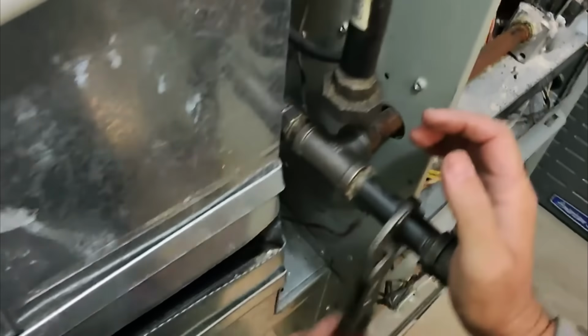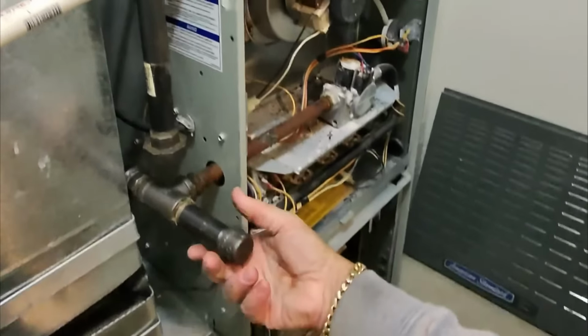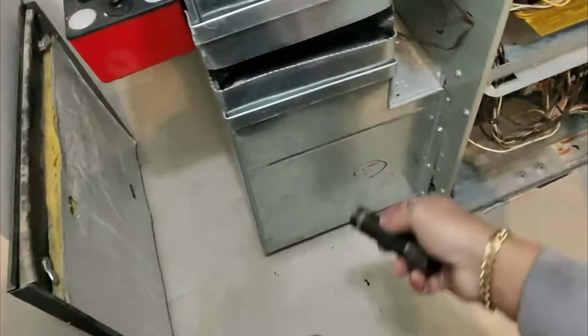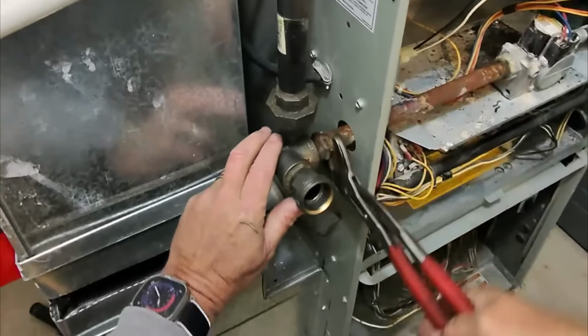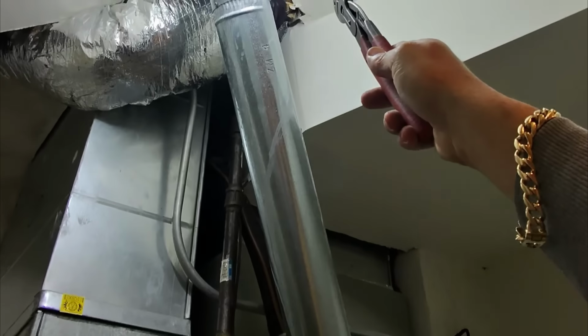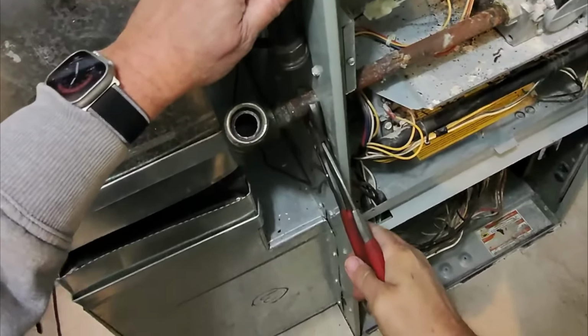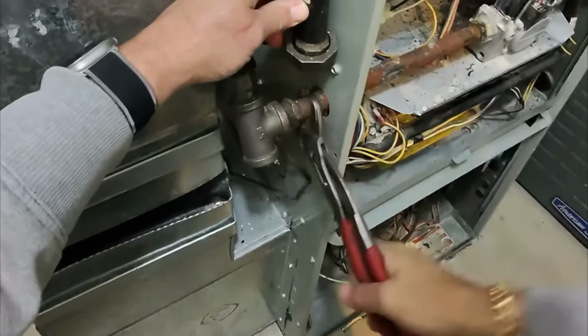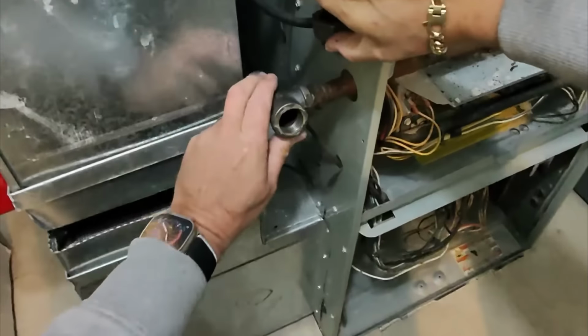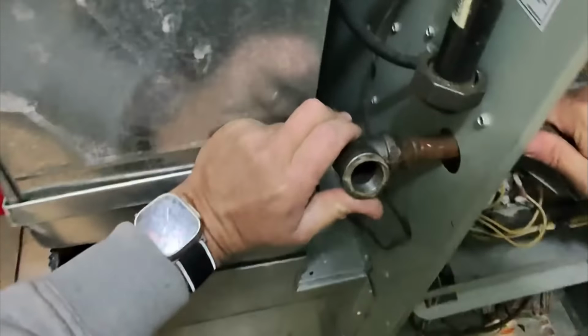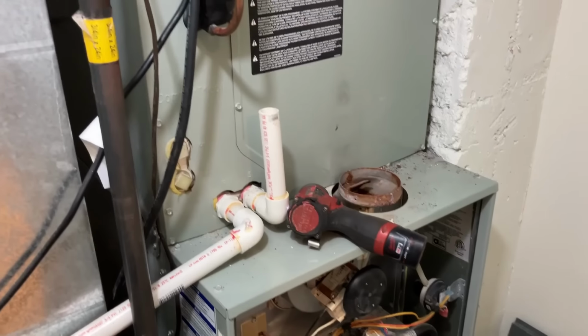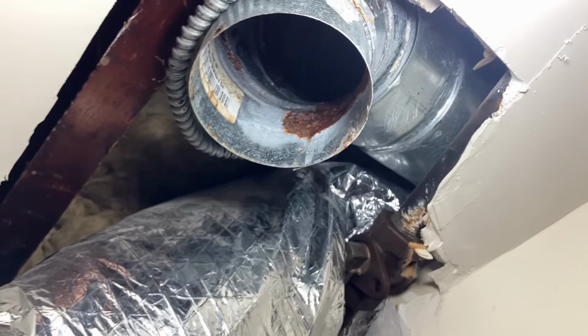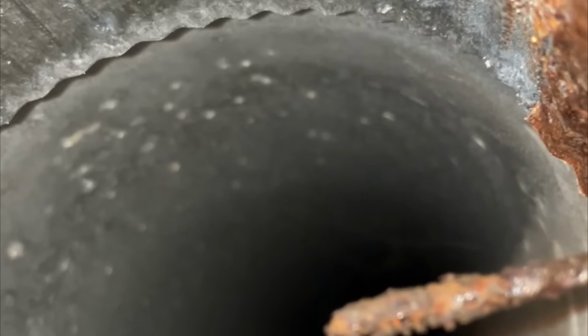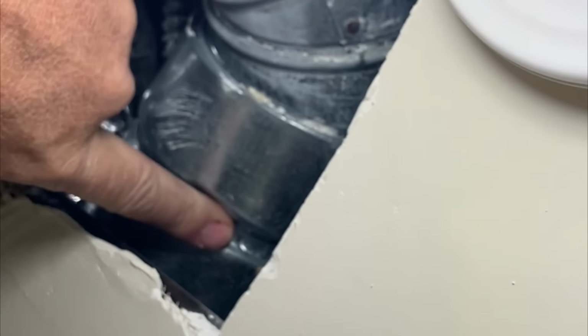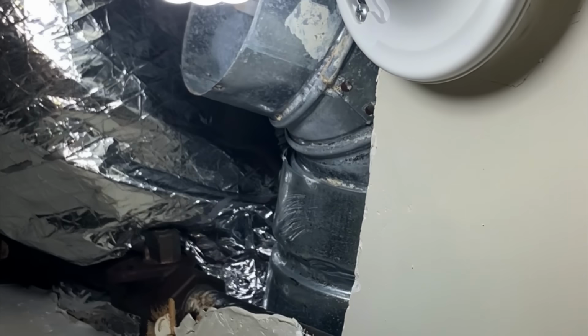All right, let's disconnect the gas. Gas valve is off there. Now, what's fascinating about this install is that whoever installed it thought it was a great idea to pretend that they're using B-vent, but they don't. And I'll show you a little bit later what I'm talking about, because it's quite sad. But as they say, or as I say, hacks bring stacks. All right, and in case you guys don't believe me, let me show you. See, that is not B-vent. Unbelievable. You put one little piece there, make it look like a B-vent, and I'll show you the termination outside, even more chaotic.